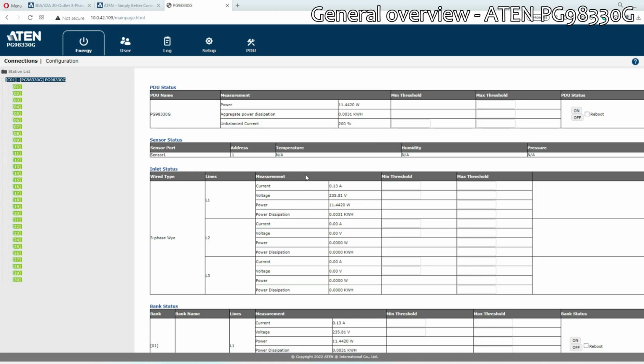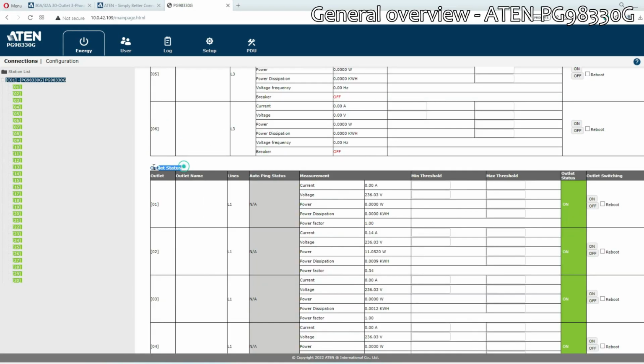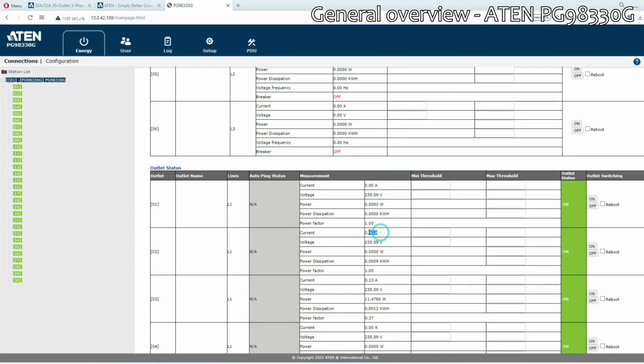Now, if you remember correctly, we installed our 4 power transmitters in bank number 2, 3, 4, and 5. Let's see if we see something on bank 2, 3, 4, and 5. So we go to outlet status. The number 1 is actually C19, and we have only used C13s, so we have to look at number 2, and we can see that the current, the amps, vary a little bit because that product does not consume that much.